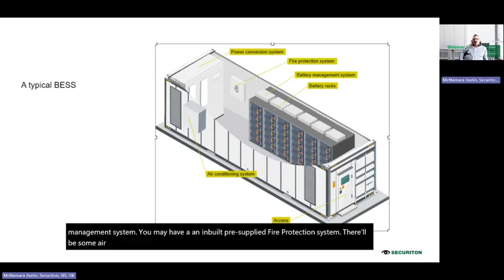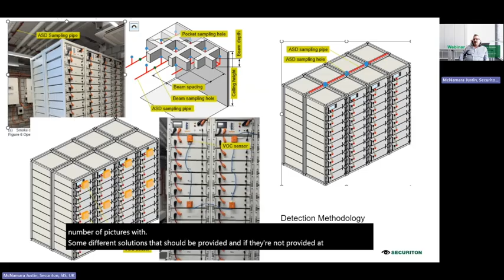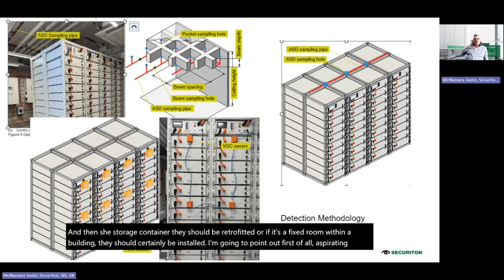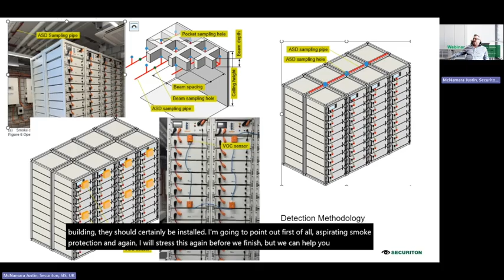What I have on screen now are pictures showing different solutions that should be provided. If they're not provided at the outset with something like an energy storage container, they should be retrofitted, or if it's a fixed room within a building, they should certainly be installed. First, aspirating smoke detection - and again, we can help you with design and layout - but aspirating smoke detection pipes should at the very least be installed within the room space, possibly above the top of the battery racks as well.